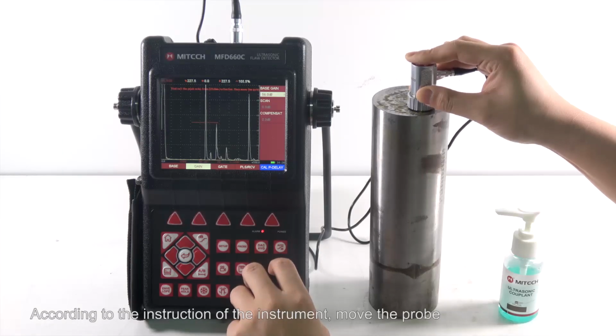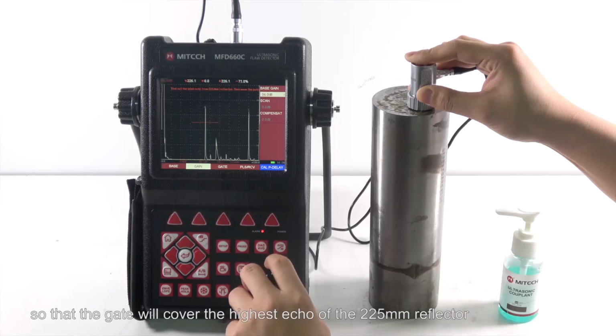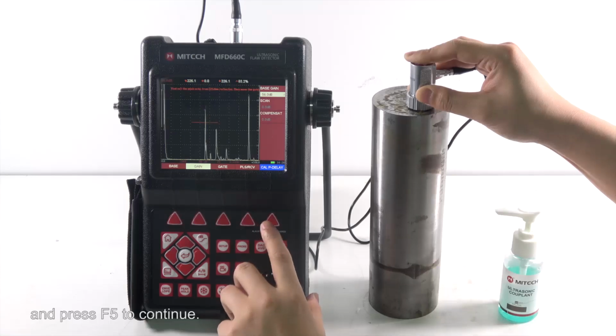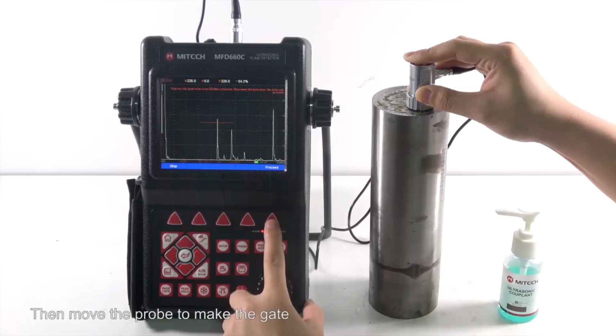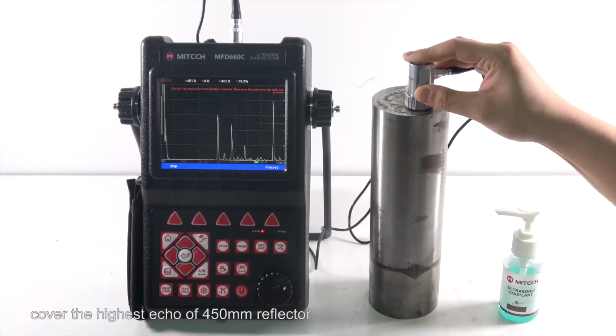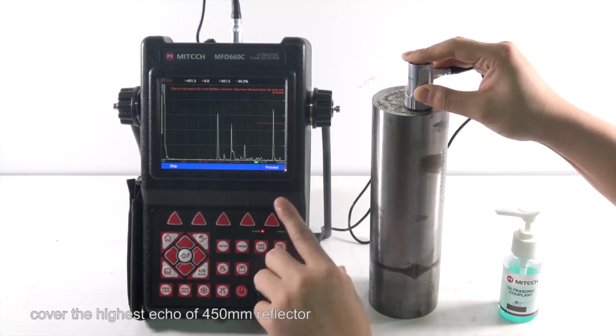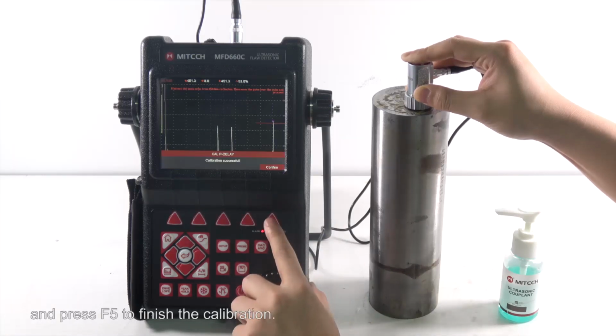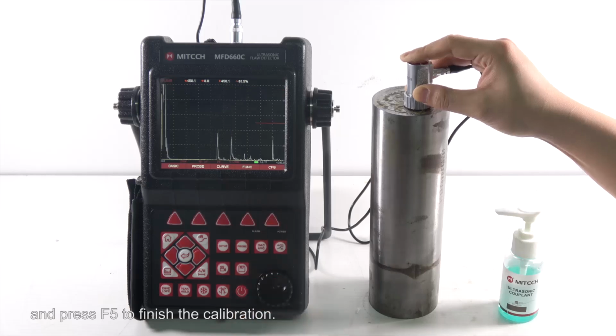According to the instruction of the instrument, move the probe so that the gate will cover the highest echo of the 225 reflector, and press F5 to continue. Then move the probe to make the gate cover the highest echo of 450 mm reflector, and press F5 to finish the calibration.